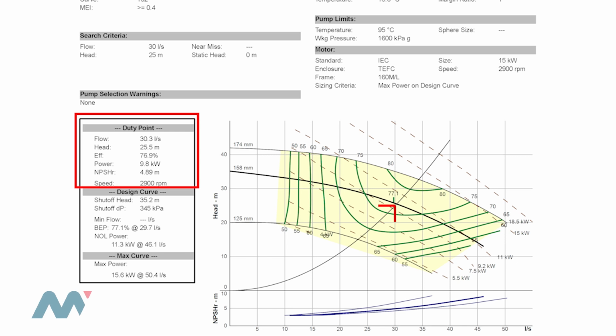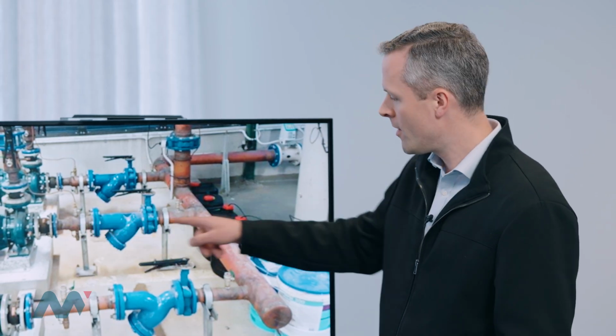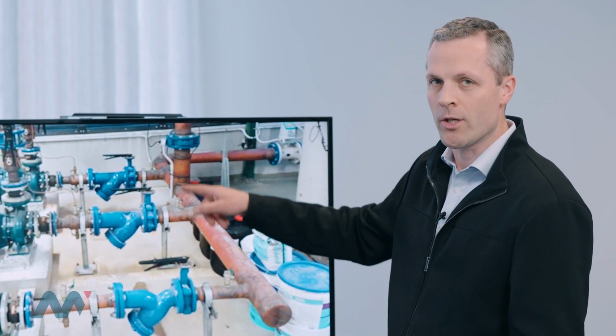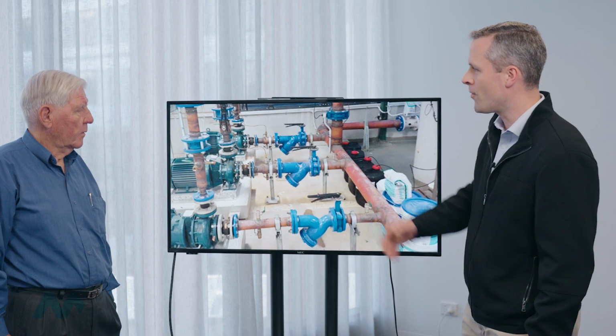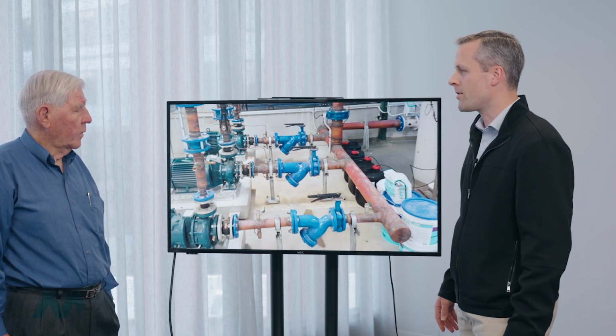Now we're going to look at the pump performance curve and see what actual pump was selected. You can see from the performance curve that these pumps have a nominal speed of 2,900 RPM and the flow rate is as detailed on the curve. So we can see when you do the calculations on the flow rate that we're running quite high velocities through 100 mil and 125 mil pipework. What's your thought around pipework velocities, Keith?